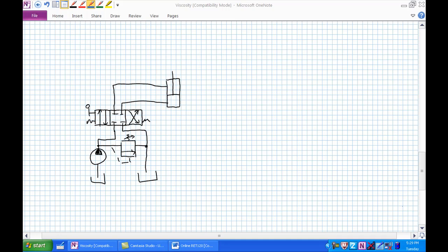Pretty obviously, what's wrong? Everything is extremely cold, including that fluid inside the reservoir. And what is the viscosity of that substance? Well, think of your cold honey. It's extremely hard to flow, and the viscosity is through the roof. And that pump is going to have an extremely hard time to pump that fluid from the system. Okay? So now let's think of the opposite case.